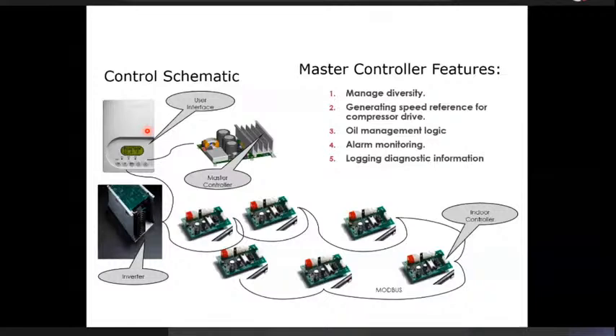And that information has to be relayed to the inverter, which in turn will drive the compressor motor RPM in a certain way. And then here we also need to get all the temperature information of the refrigerant. So not just the room temperature, but we also need the compressor data performance related to temperature and pressure. So all of that it needs to do. Then there is some oil management logic. What happens is, at a certain periodic interval, the compressor must be made to run at full capacity, so that all the accumulated oil, which could be stuck in different parts of the pipeline, is brought back to the compressor. And then any diagnostic information has to be logged, any alarm monitoring has to be done, so all that is included.